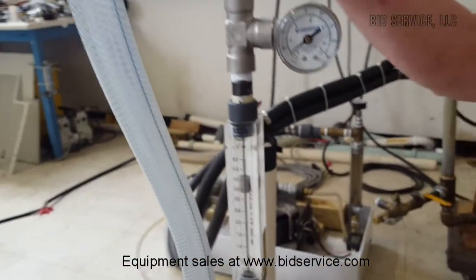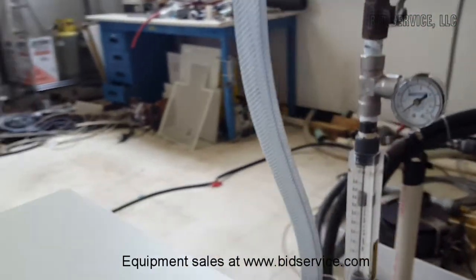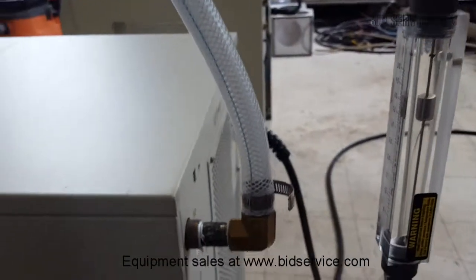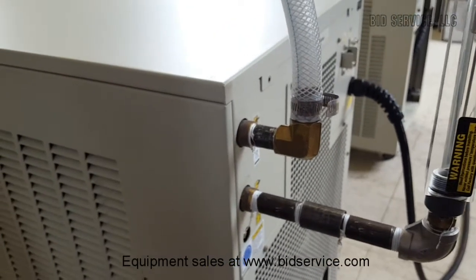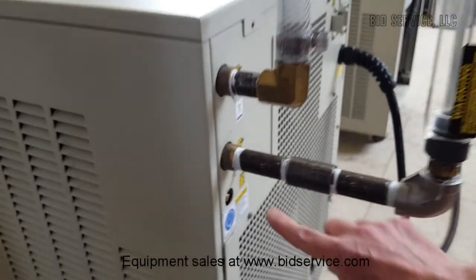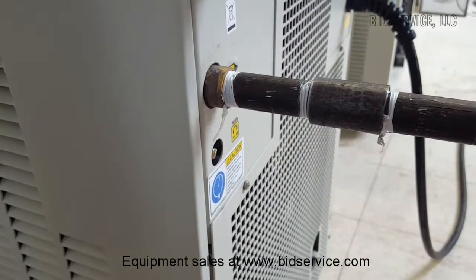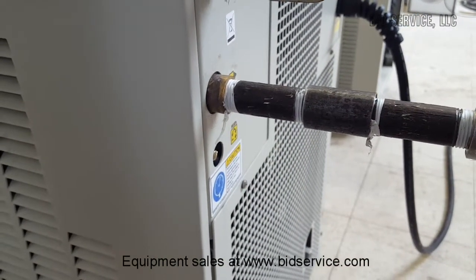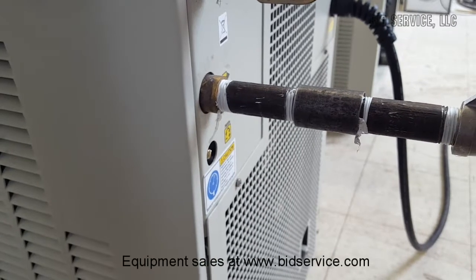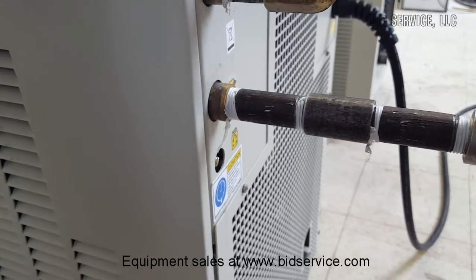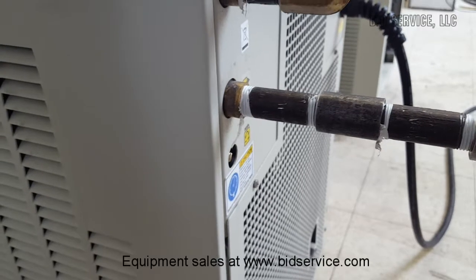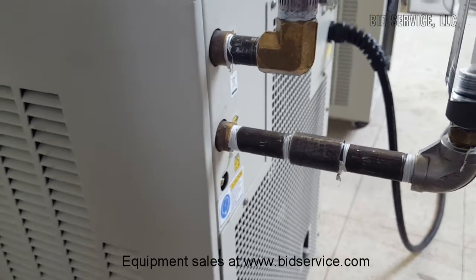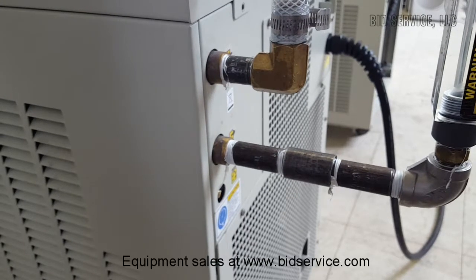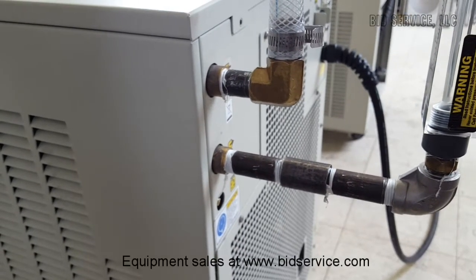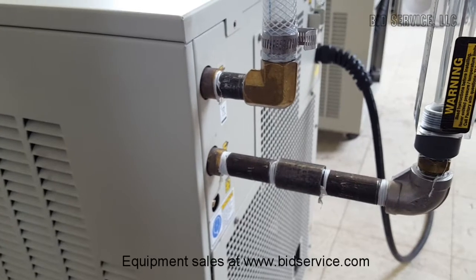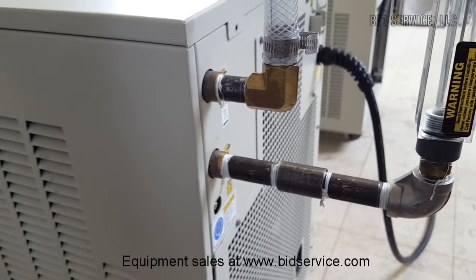One other note regarding its operation is if you also look behind here, you'll see just below the supply output is a screw. Now, this is a bypass valve that allows you to change the output pressure. If it's turned all the way clockwise, it would allow maximum pressure. Turned counterclockwise, it would allow you to drop the pressure in here.